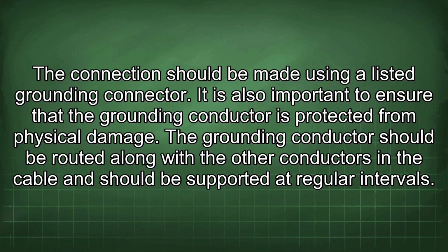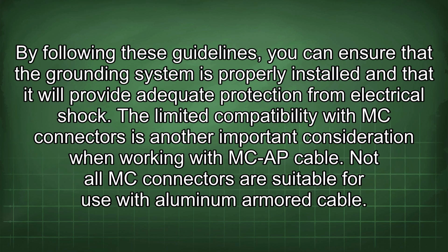It is also important to ensure that the grounding conductor is protected from physical damage. The grounding conductor should be routed along with the other conductors in the cable and should be supported at regular intervals. By following these guidelines, you can ensure that the grounding system is properly installed and that it will provide adequate protection from electrical shock.